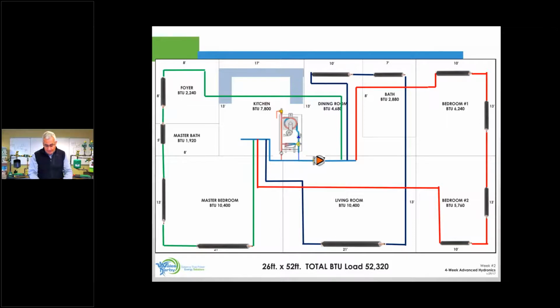So plug that number into your calculator, please. 98 times 1.5 times 0.04. We should get 5.88 feet of head. We can call that 6. All right, write that number down.